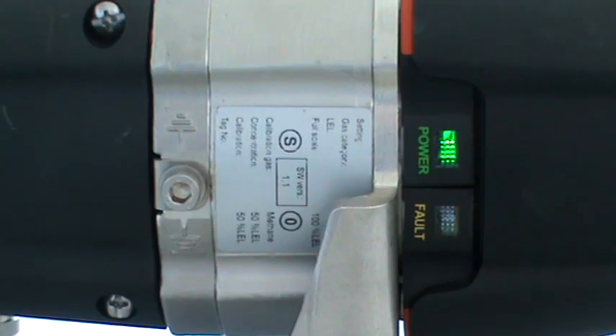Now you see that the status lights are changing their status again, and the green status light is now flashing just once. You can see the light is on, off, etc., etc. And this means that the calculated 0-point drift is within range 1, the smallest range of drift around the 0 point, the best possible calibration result. Speaking generally, a just once flashing green light always proves that the instrument has drifted just very slightly, or maybe not at all. Now you have 2 options.